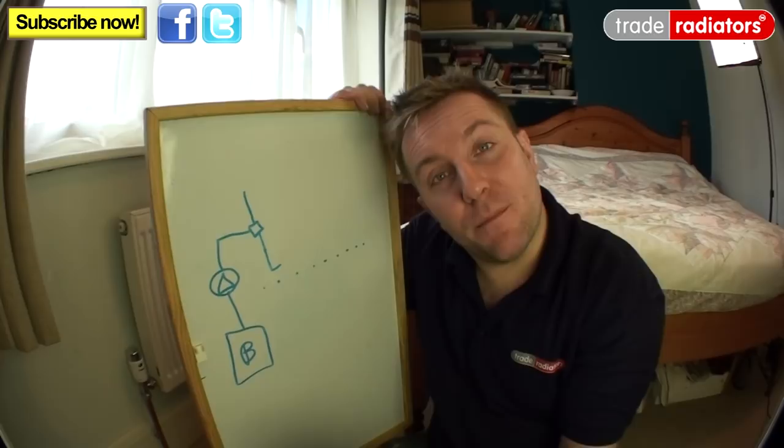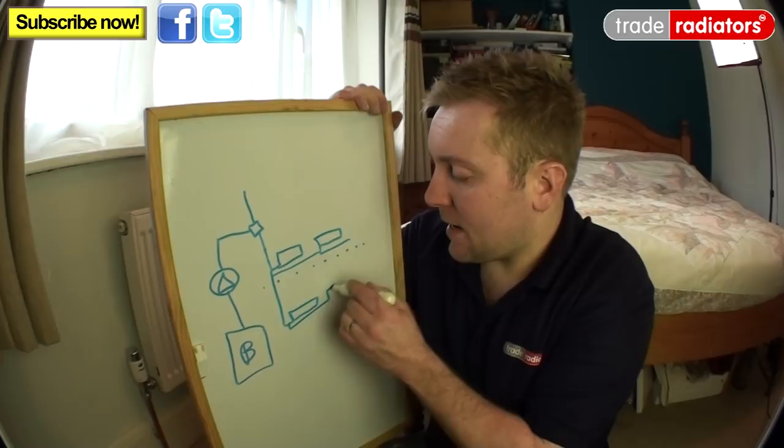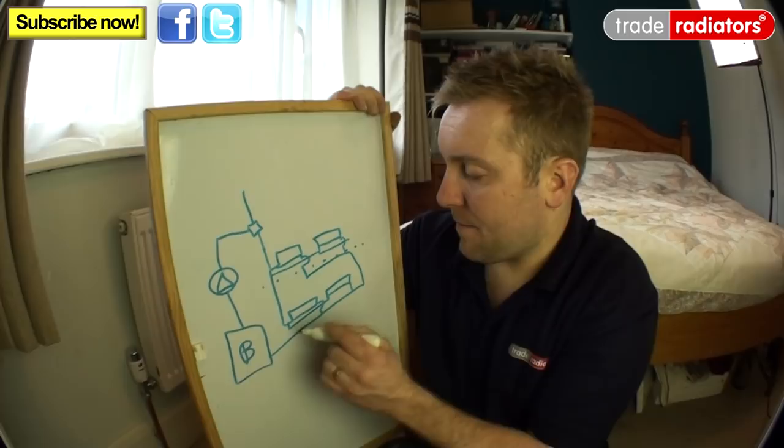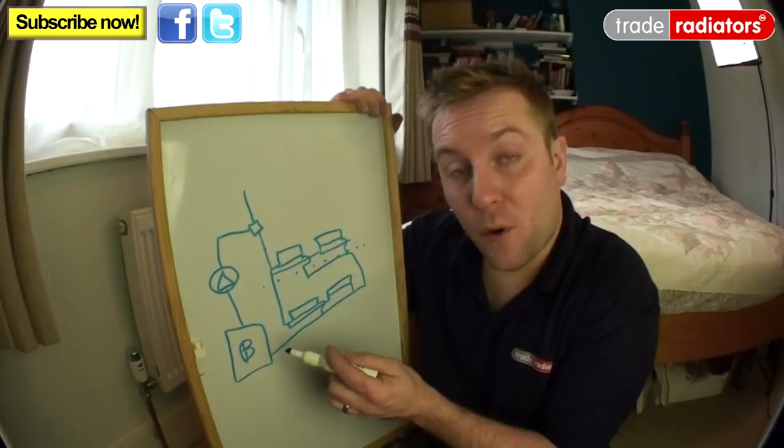If we look at this system here, we have a radiator here, a radiator here, and then downstairs we have another radiator there, and another radiator there. They all have common returns going back to the system and back to the boiler. Basically, this radiator is first in line and also it's upstairs, which means it's going to get loads and loads of flow from the boiler and the pump, and then it's just going to go back to the boiler and not go around the other radiators.